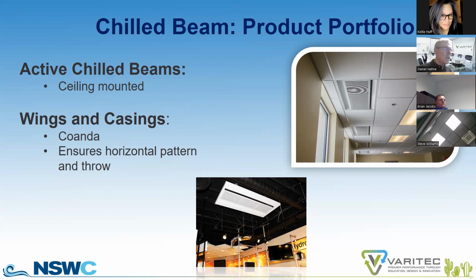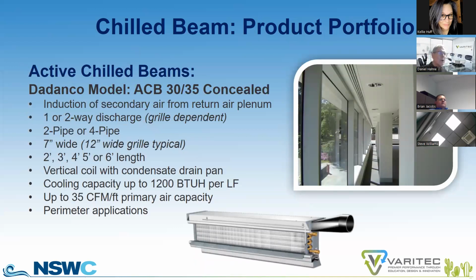So if you do have an open ceiling and you are looking at laying out active chill beams, you'll notice that the width of these beams are much larger than a conventional chill beam mounted in a ceiling. And the purpose for that is so that we get proper dispersion of the air and thorough mixing in the environment. But be aware, there are other active chill beam solutions that could meet an architectural design. There are linear diffusers where the coil is actually vertically set within the chill beam casing. And that allows for linear discharge configuration, so you don't have a box of metal located in areas that are not sensitive to that visual potential obstruction. So there are vertical chill beams, and I'm excited about this unit.